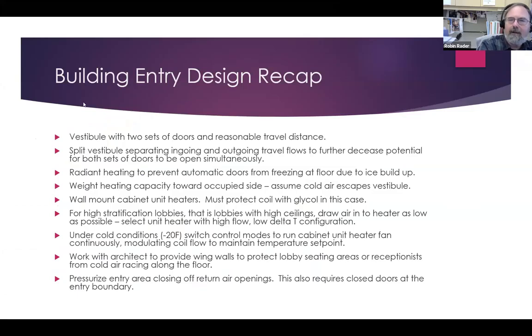Okay, so I'm just going to recap building entry design real quick. Vestibules with 2 sets of doors and reasonable travel distance. Split the vestibule, separating incoming and outgoing travel flow, decreasing the potential of both doors open simultaneously. Radiant heating to prevent automatic doors from freezing to the floor due to ice buildup. So if you've got a new facility and you're going to put in electronic doors on the outside, get radiant heat into that vestibule. You'll still need a cabinet unit heater. Radiant heating doesn't have a high enough heating density to heat the space all by itself, but it will keep that track from freezing.